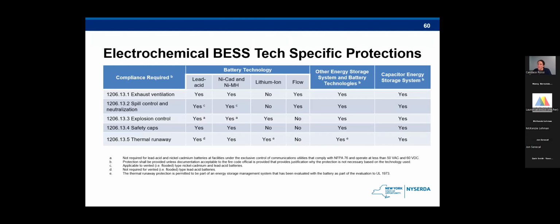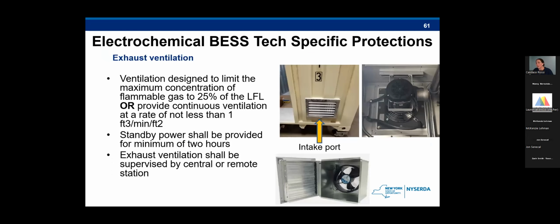So I guess I'll highlight one more thing on this table, is that you can see for lead acid that all 5 of these requirements are required, and similar with nickel. And then basically lithium ion is really the only one that only has 2 out of the 5. One of the reasons why for spill control is that lithium ion doesn't have a liquid electrolyte like lead acid does, so it's not at risk of spill. And we'll continue going through. I'll try to highlight the differences between the battery techs as we do that.